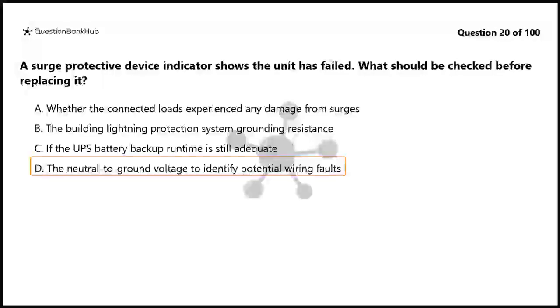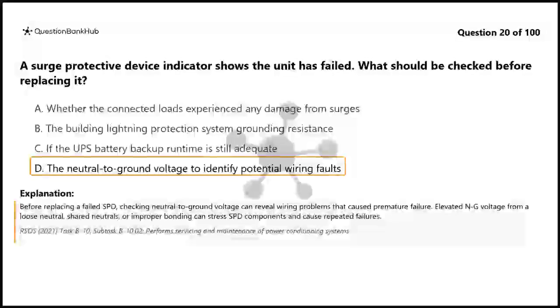The correct answer is D. The neutral to ground voltage to identify potential wiring faults. Before replacing a failed SPD, checking neutral to ground voltage can reveal wiring problems that caused premature failure. Elevated NG voltage from a loose neutral, shared neutrals, or improper bonding can stress SPD components and cause repeated failures.